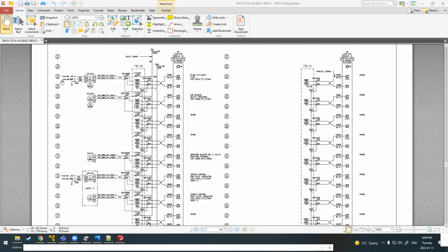This flow meter has 120 volts coming into it. There's wire labels for that, and it's grounded out on this side. So it has its own power. It is not being powered from the PLC. It has signal wires coming out of it that get wired into input 10-0. And that's all the information we get here. We do have a tag for what that device would be inside the PLC, but we do not know the range of that. So we know that there's a flow meter.